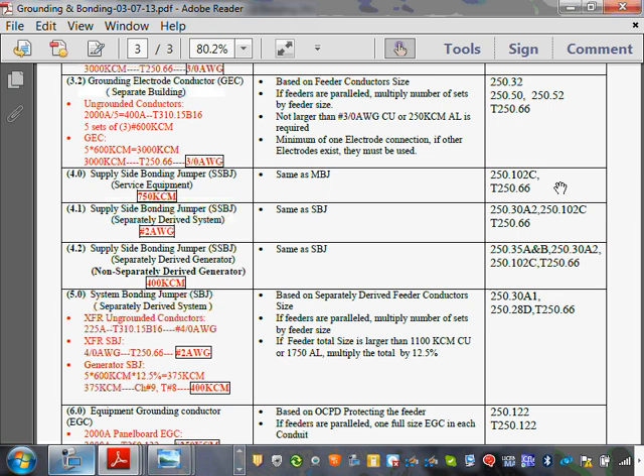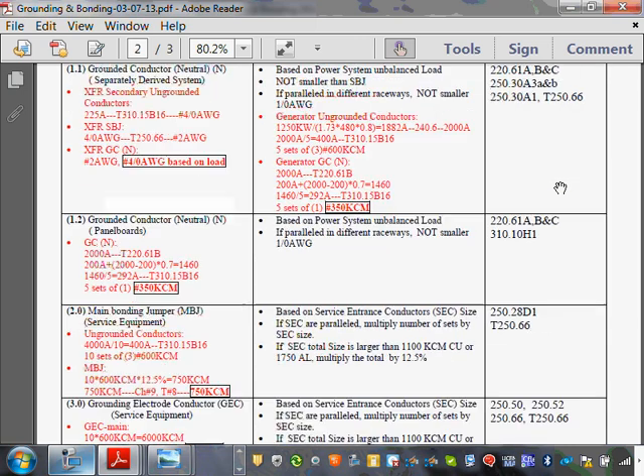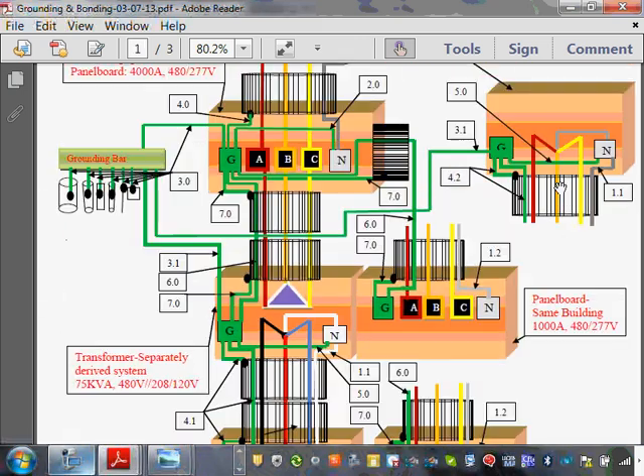Or Southwire, I don't know if they're still in business, Southwire will make this size for you for an arm and a leg, right? So 400 kcmil, that's your system bonding jumper that you're going to take the neutral to the ground, bond them together. If the manufacturer of the generator already sized this one for you guys, you don't mess with it. It's listed equipment, no messing with it. So that's my system bonding jumper for the generator. What size did we come up with? 400 kcmil.